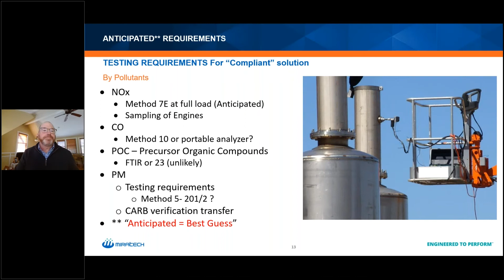So what are the operational modifications if you put in these controls on your engine? How are you going to have to operate your data center differently, or your engine? The SCR system, you're going to have to do a full load test. How you do that initial compliance test after commissioning is up to you - you rent a load bank or put in a permanent load bank. Most folks, I believe, will rent a load bank for this test and hope the testing interval will be such that you won't have to rent one again for a couple of years.